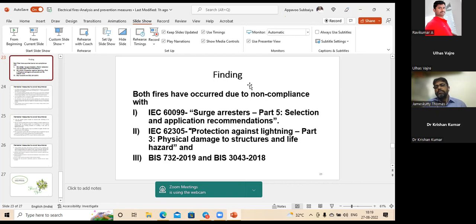As was told, we are in a Faraday's cage, but this cage is not accepted. If there is no cage, you provide something like a grid, as you provide an earth mat in the substation. You provide a mesh on the rooftop. If it is a lean-to roof, you provide a sufficient type of lightning mast. There can be a combination of mast and mesh.